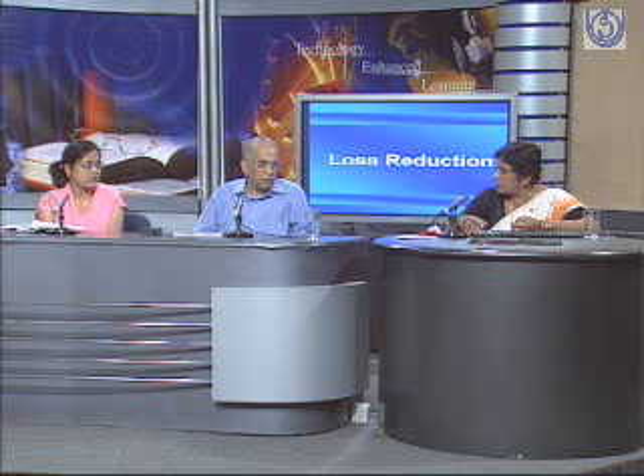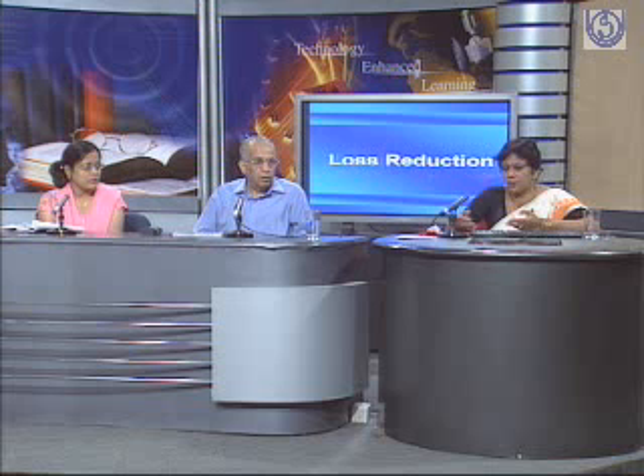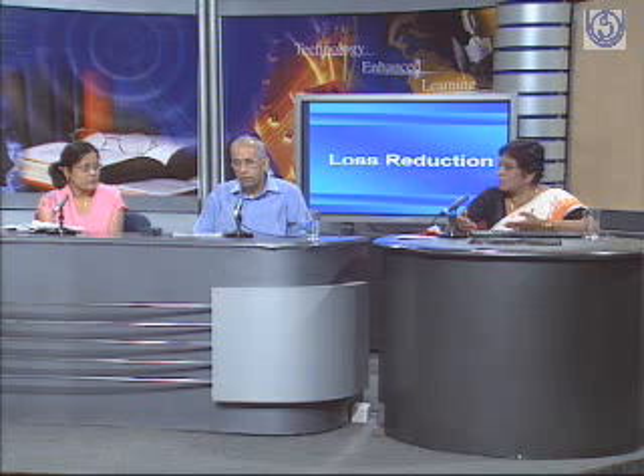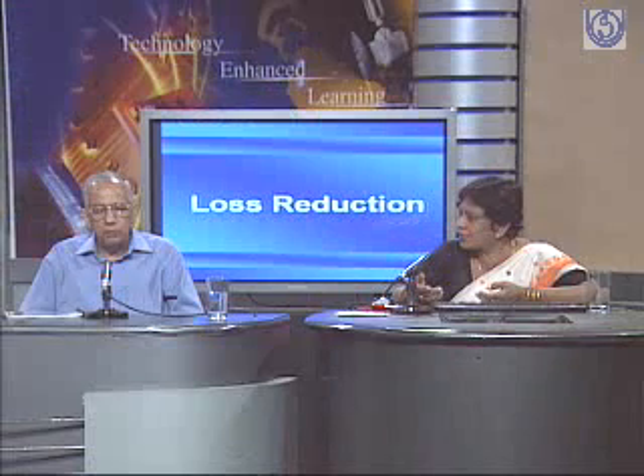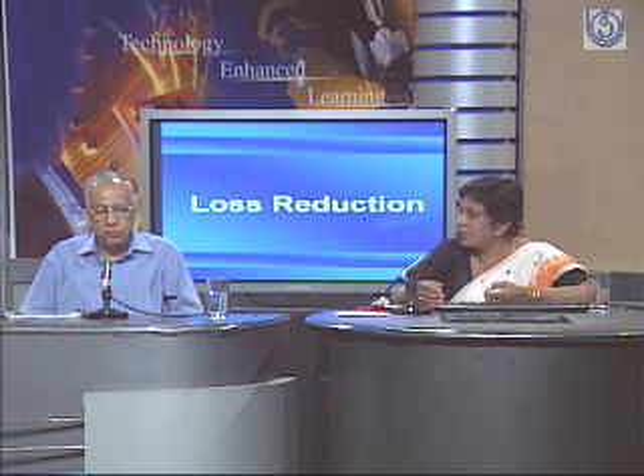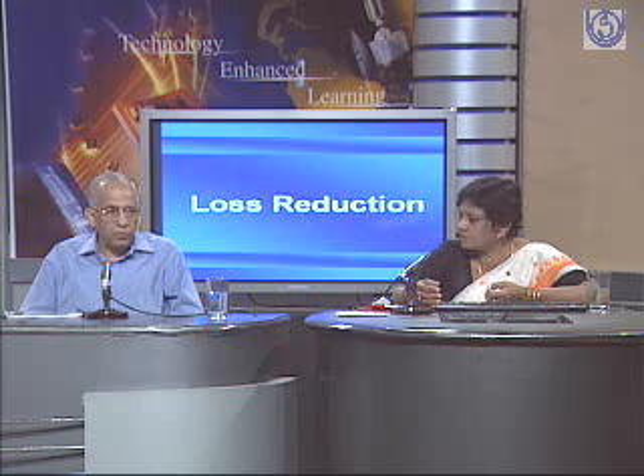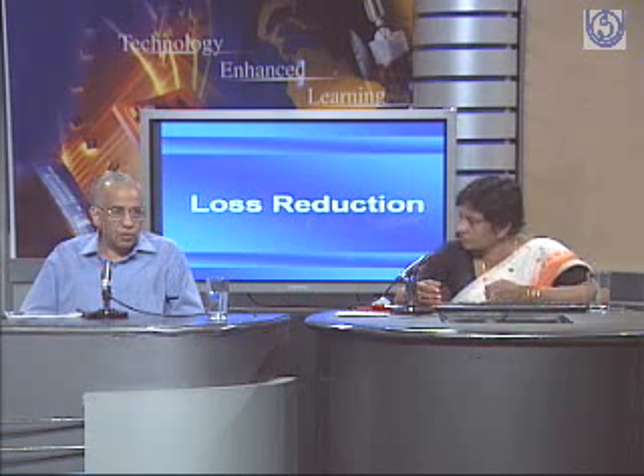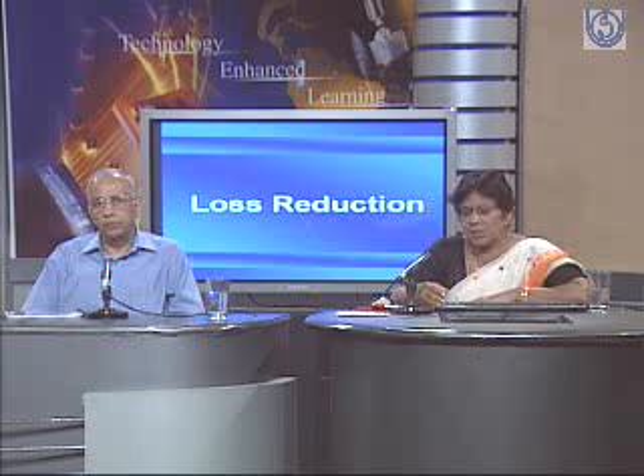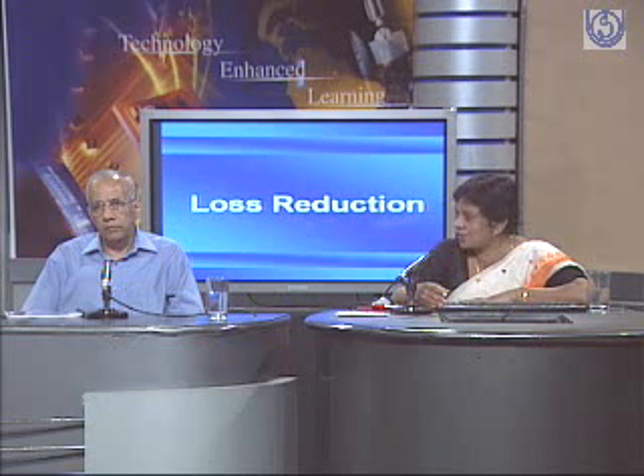If someone injects a high voltage, then anything can happen because the pulse will become erratic. That is in case of tampering of the meter by injecting a high voltage, but in regular conditions there is no question of it. But technically it is feasible. When there is an injection of a high voltage, the pulse will get erratic, so what reading it records will depend on how the electronic circuitry reacts to that pulse. That is normally used by people to reduce their bills. Yes, it can be used, and it is being used. It is one of the methods for tampering.